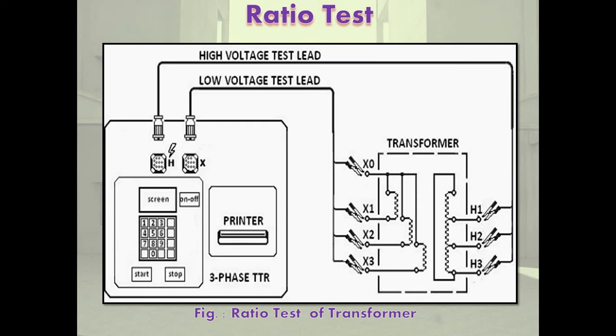In the previous lecture, we discussed different types of classification of tests on power transformer, like type test, routine test, special test, and commissioning test. Now, type test and routine test. The difference is that a type test is performed on a single transformer of one type to check conformance with ratings and characteristics, while routine tests are made on every transformer before it leaves the factory.